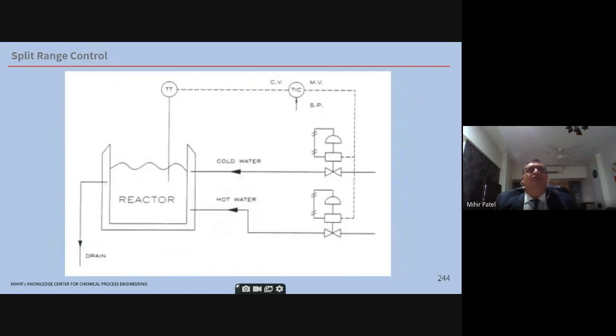Split range control is also there. Let's say the reactor is there, and you are controlling at 80 degrees centigrade. It's an exothermic reaction, and 80 becomes 82. What will happen is, the split range controller will send a signal, it will reduce the hot oil valve, reduce the hot water valve, and open the cold valve. So this is a split range control to maintain 80 degrees in the reactor.